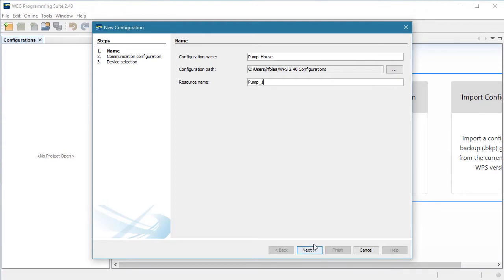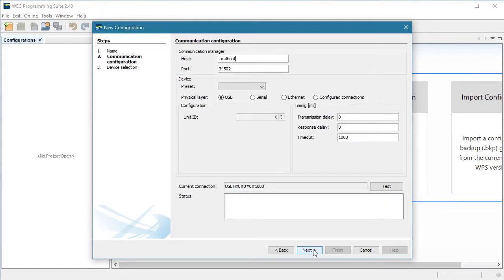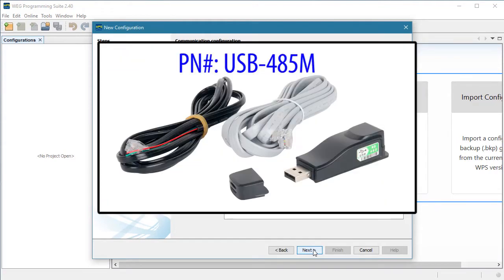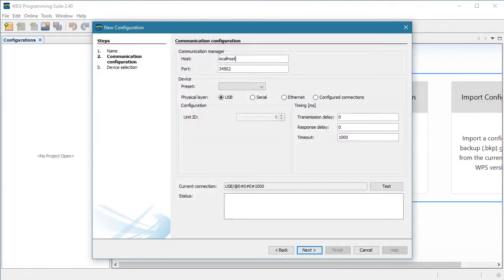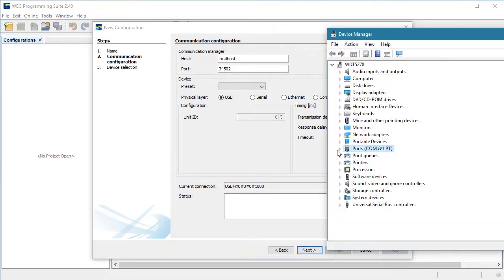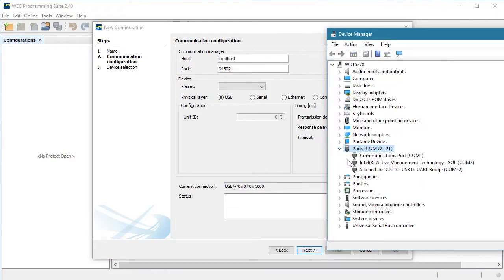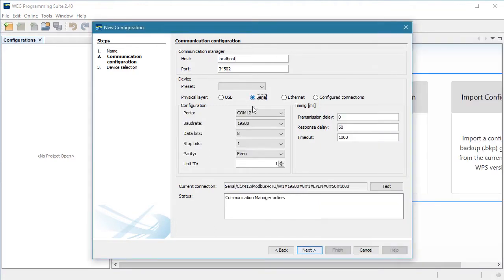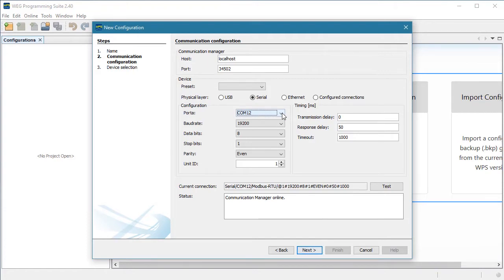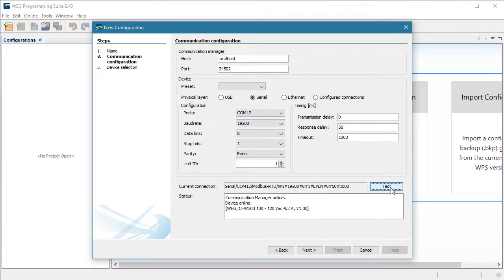I'm using a 485 COM module and this USB to 485 adapter to communicate with this PC. If we plug the USB adapter into the PC and open the device manager, we see that the PC registers that as a serial port at this port number. So we select serial port and we put that COM port number here. The rest of these are the default values for the drive and I haven't changed those so I'll hit test and we see we are online and ready to go. Perfect.